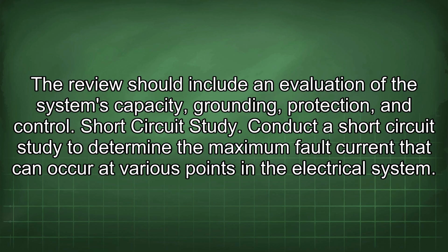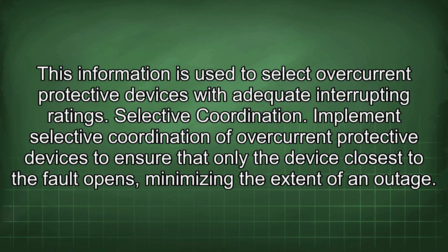Short circuit study. Conduct a short circuit study to determine the maximum fault current that can occur at various points in the electrical system. This information is used to select overcurrent protective devices with adequate interrupting ratings.